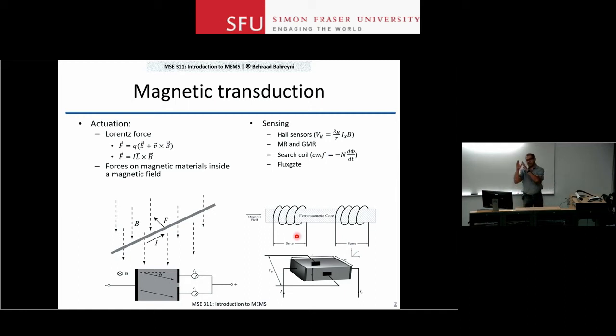What happens then is that they keep the drive signal very close to that saturation limit. The amplitude of the second harmonic will be very sensitive to where you are. And the saturation curve, on the other hand, is affected by external DC magnetic fields. So if you have, let's say, a 1 microtesla increase in the outside magnetic field, it moves the saturation curve a tiny bit, and you get a different amplitude for the second harmonic of the signal that you're picking up at the sense electrode. These devices are very, very sensitive. The good ones can measure down to nanoteslas. Typically, for a Hall effect sensor or a magnetoresistive sensor, you're talking about tens of microteslas. Flux gate sensors can go down to the nanotesla range.